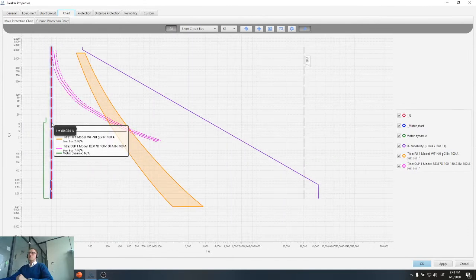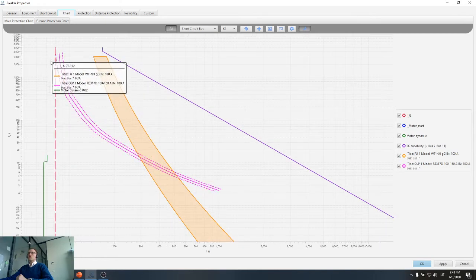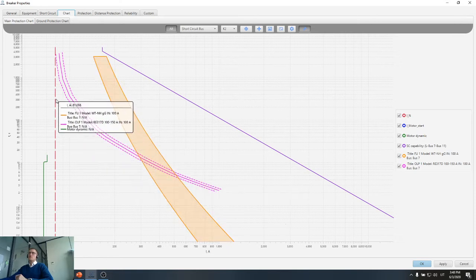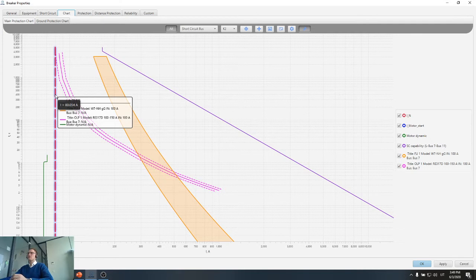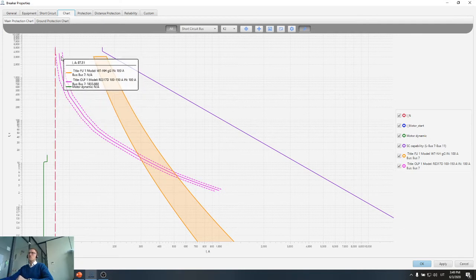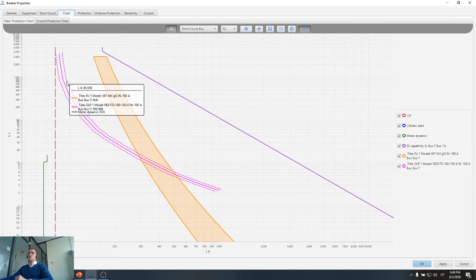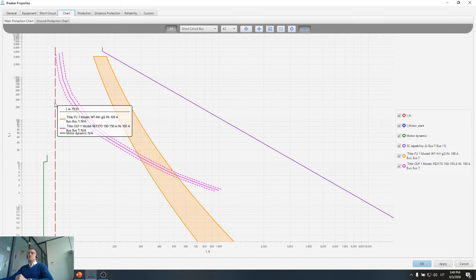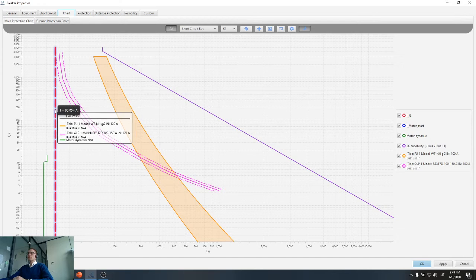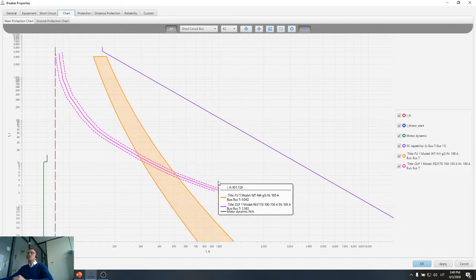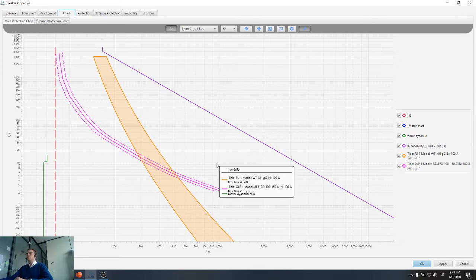Here the red line shows normal current. Here we can see our overload protection device time and current curve, and in case the fuse current exceeds the calculated maximum current, the overload protection device will trip in order to avoid overheating of the fuse. This kind of thing can happen in case of high harmonic levels. Also, if the insulation of the fuse is affected, the current will also increase, and this overload protection will disconnect the fuse and will protect the substation from fire. Let's say if the fuse explodes after the short circuit.